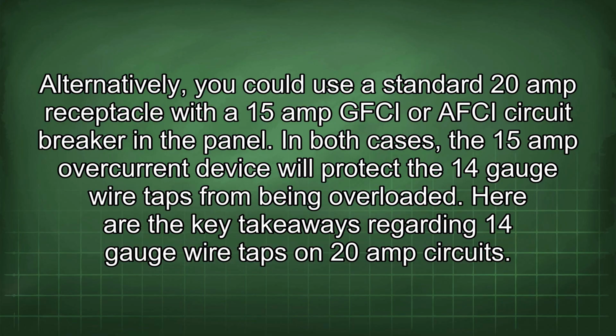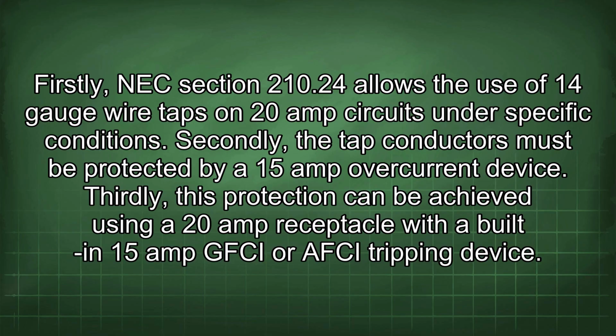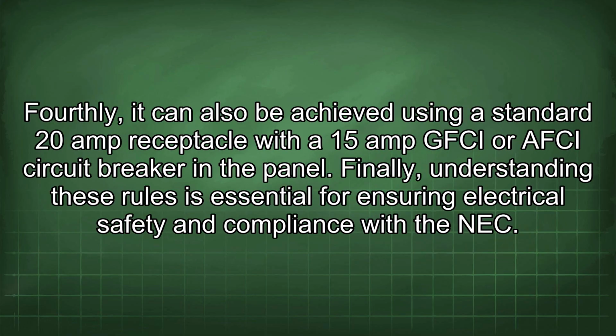Here are the key takeaways regarding 14-gauge wire taps on 20-amp circuits. Firstly, NEC Section 210.24 allows the use of 14-gauge wire taps on 20-amp circuits under specific conditions. Secondly, the tap conductors must be protected by a 15-amp overcurrent device. Thirdly, this protection can be achieved using a 20-amp receptacle with a built-in 15-amp GFCI or AFCI tripping device. Fourthly, it can also be achieved using a standard 20-amp receptacle with a 15-amp GFCI or AFCI circuit breaker in the panel. Finally, understanding these rules is essential for ensuring electrical safety and compliance with the NEC.